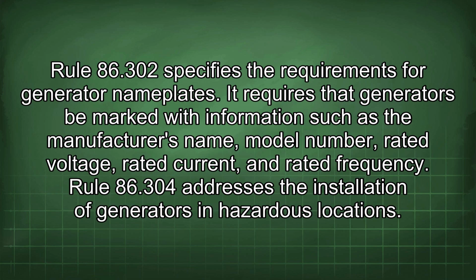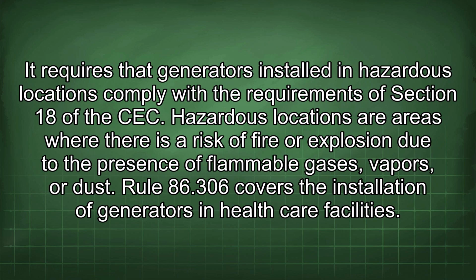Rule 86.302 specifies the requirements for generator nameplates. It requires that generators be marked with information such as the manufacturer's name, model number, rated voltage, rated current, and rated frequency. Rule 86.304 addresses the installation of generators in hazardous locations. It requires that generators installed in hazardous locations comply with the requirements of Section 18 of the CEC. Hazardous locations are areas where there is a risk of fire or explosion due to the presence of flammable gases, vapors, or dust.